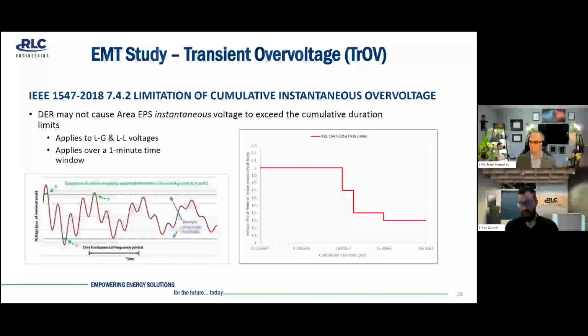But with modeling established, let's get into the analyses. So first up, we have transient overvoltage, or TROV. And this is evaluated per IEEE 1547-2018, section 7.4.2, limitation of cumulative instantaneous overvoltage. Wow, that's a mouthful. I'll only say it once. But effectively, cumulative voltage durations are measured per this graph shown on the left from 1547 and held to the criteria of limits shown on the right.